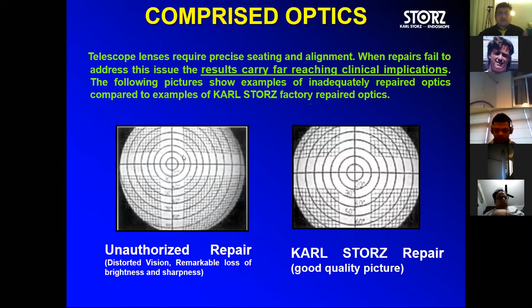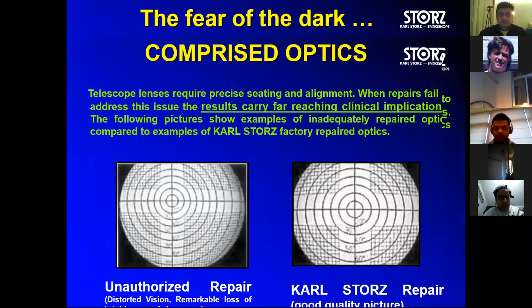So try to get a proper service done at the proper company workstation, and do not compromise on these repairs, because you will not enjoy your surgery with true image. Now let's see the other issues which come. When the surgeon is using the flexible endoscope through the sheath, he has to keep this black knob which moves from 0 degree to 270 degree.